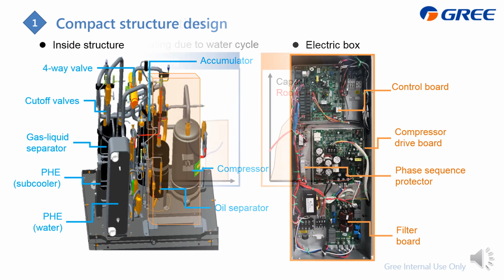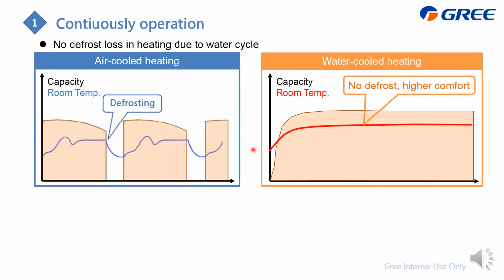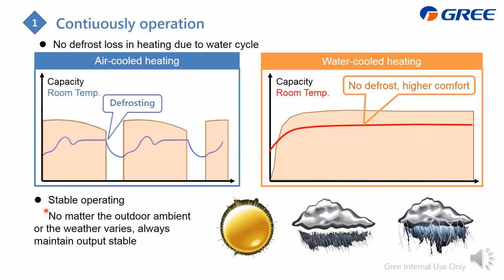And for the water cool, when it is doing heating, compare it with the air cool. For the air cool, it needs defrost if the outdoor temperature is low, and for the water cool, there's no need because we just need to ensure the water temperature is not that low. It's okay. And also we don't care about the outside weather, whether it is sunshine or rainy or snow, it is the same.